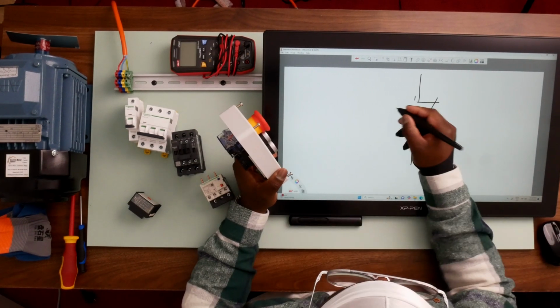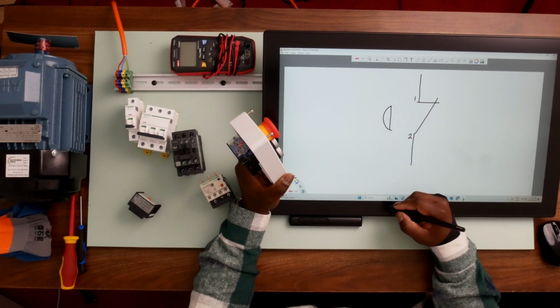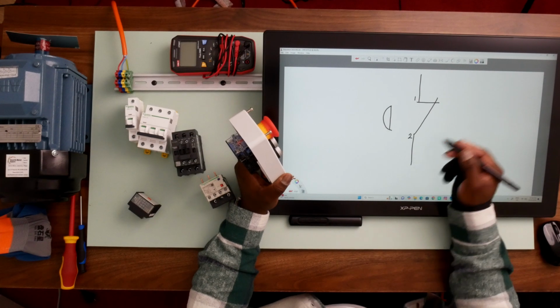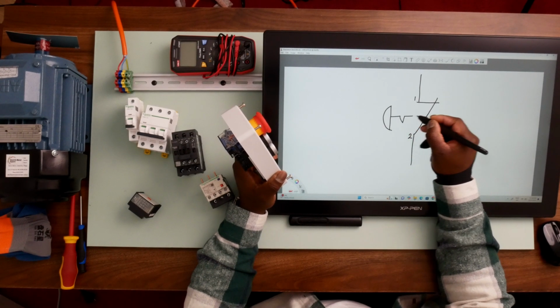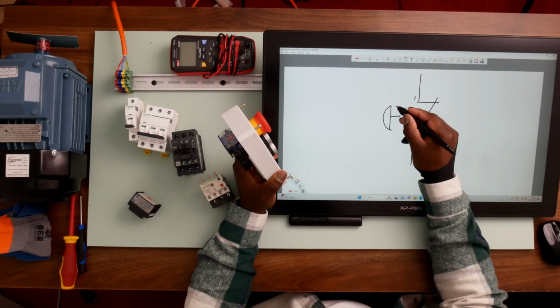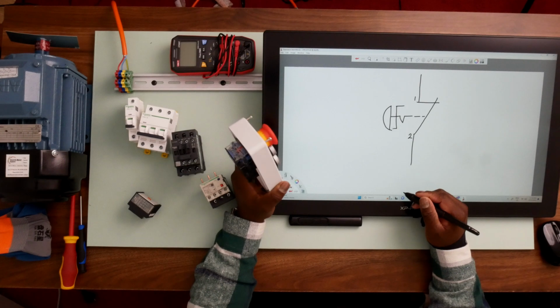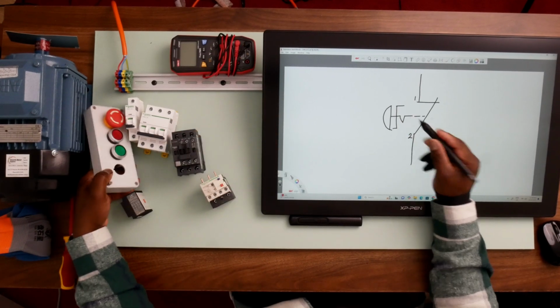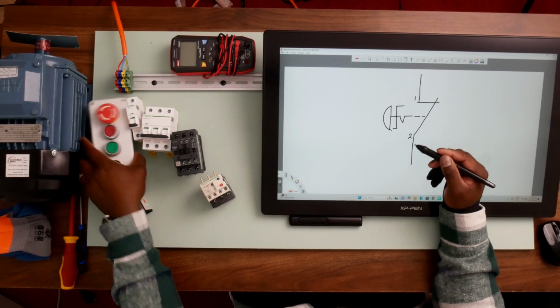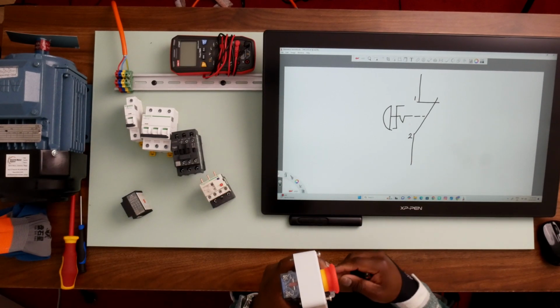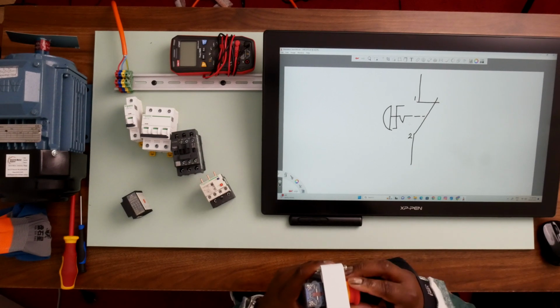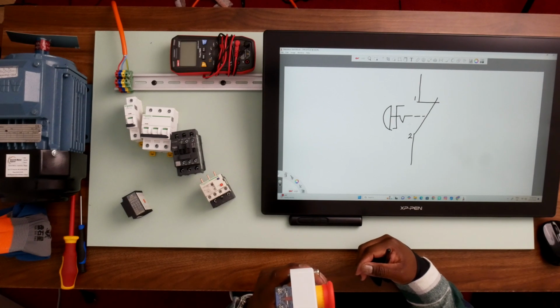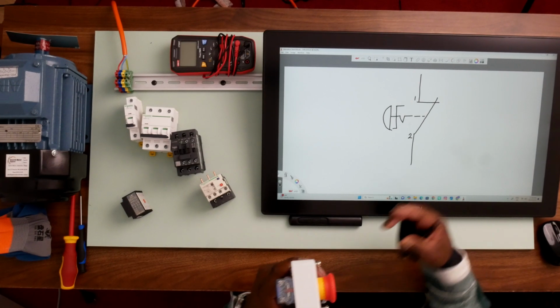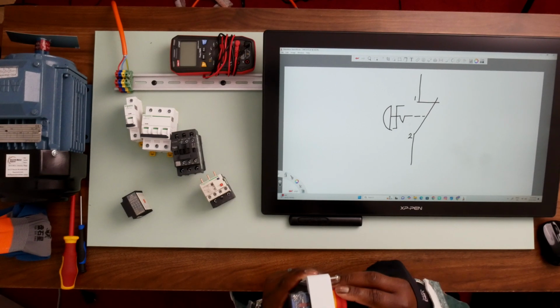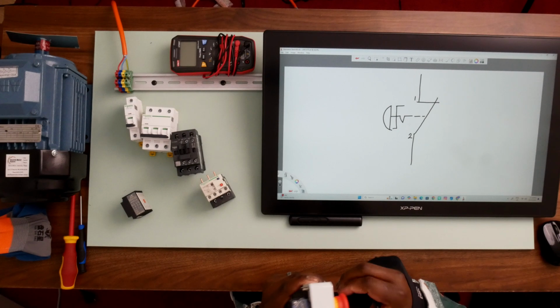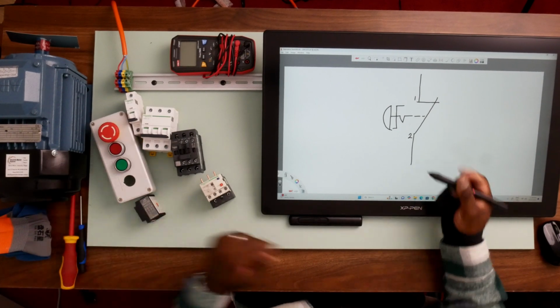A mushroom head e-stop, we draw it like this. So this is the graphic symbol for a mushroom head e-stop, and then this part here tells us that it's an e-stop. And for this one, okay, so this part tells you that it's a latching contact. This one tells us that it's a latching contact. And this type of e-stop that I have here, when you press it, it latches, and in order for you to release it, you have to twist it to release. So this one is a twist to release e-stop. We have different types of e-stop. Some of them are pull to release. You push them in, and then to release, you simply pull them out. But this one is a twist to release. So the symbol for the twist to release e-stop is like this one.